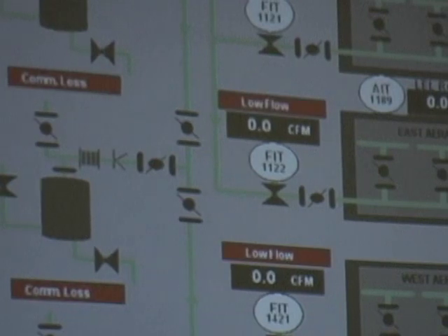And that's where that snuck in at. But this only has a low flow, so that for whatever reason, your diffusers are clogged up or something like that, so you don't actually have air going through this particular valve, that would give you a low flow alarm.